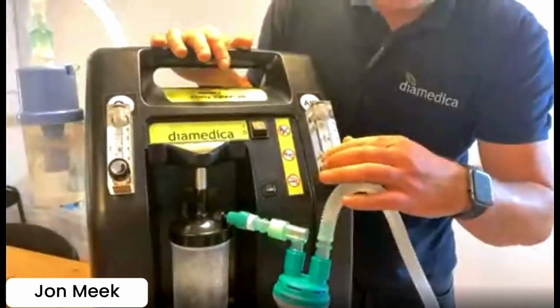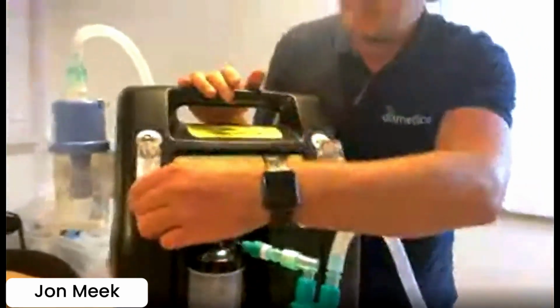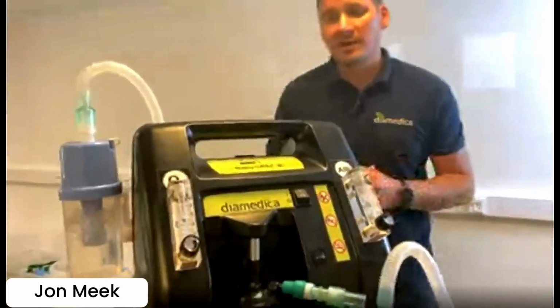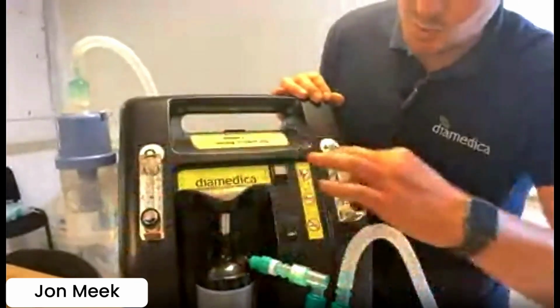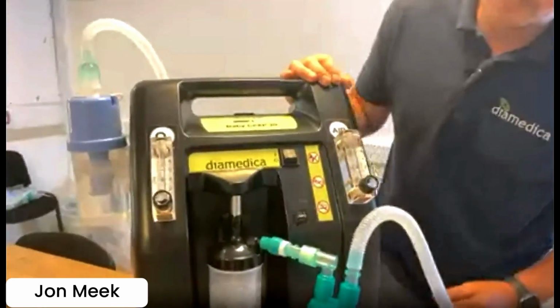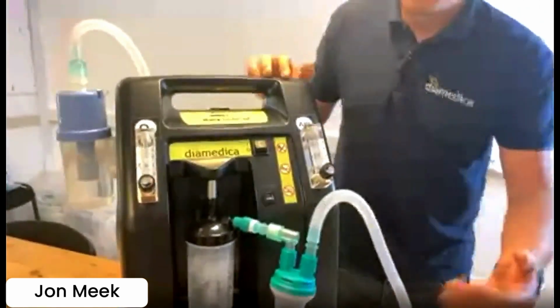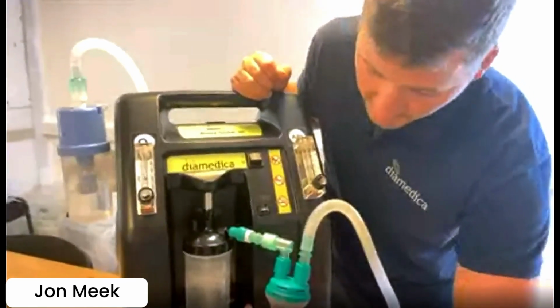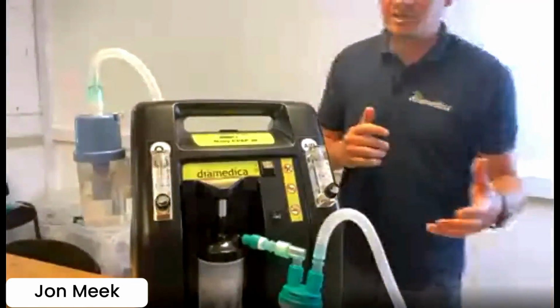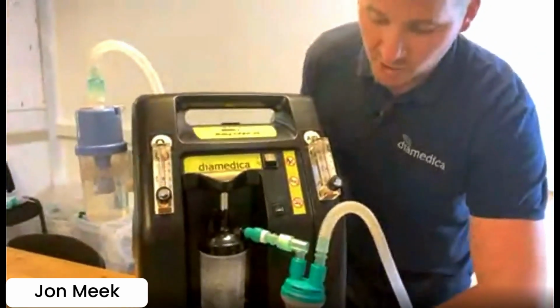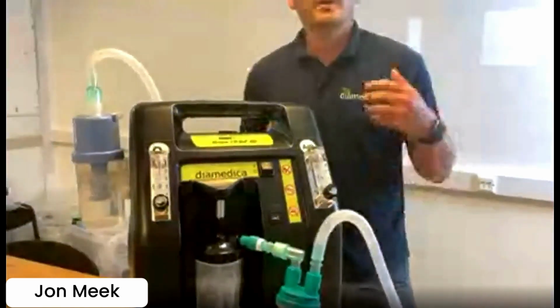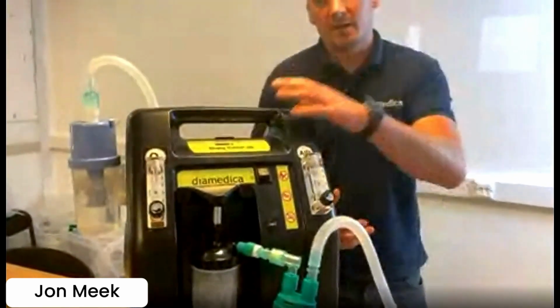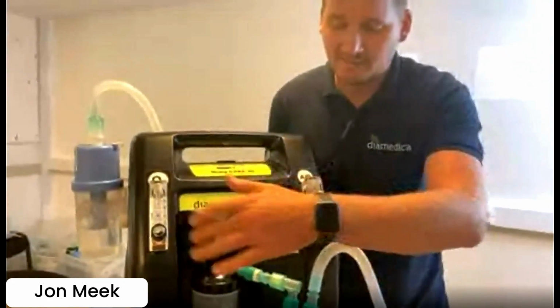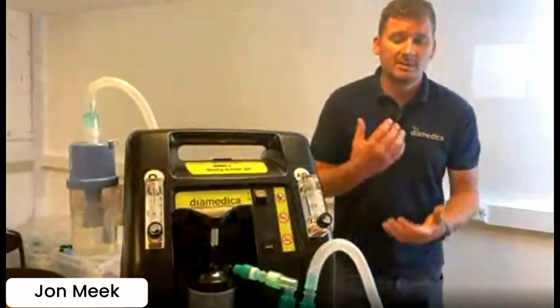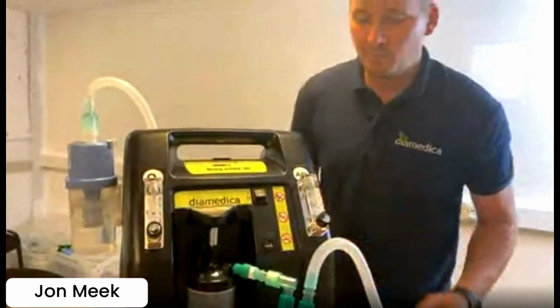So we've set the flow rates to what you require. I know the light's still orange. It'll turn very quickly to green because we've just been running it. Use the center of the ball, your diameter, to read the machine. You can see that it's bubbling in here, and it's warming. Once it warms up, it will be using the warm air to warm the humidifier. Inside as well, we warm the oxygen before it comes out of the common gas outlet. So we internally warm as well to provide the temperature warming of the machine.